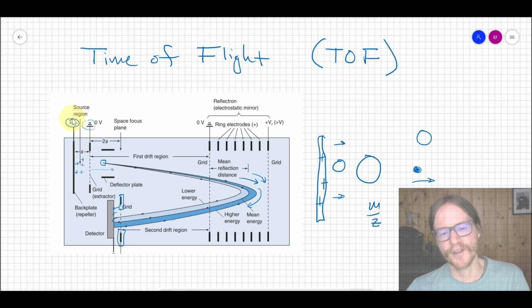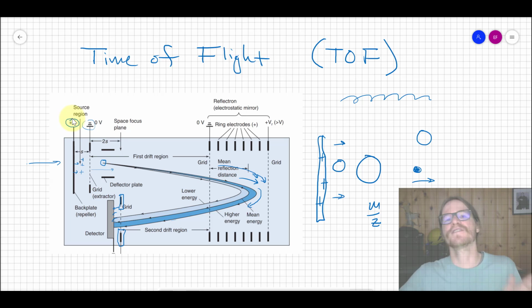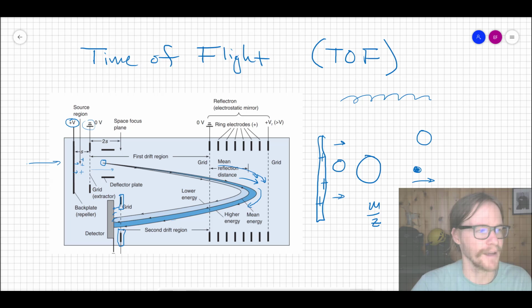And so the principle is very different. Instead of using a radio frequency electrostatic potential applied between 4 rods to change the stable trajectory of an ion, here we're really allowing everything to go through, but they're going through at different rates based on that original push that they get from the repeller electrode. They penetrate further into the set of ring electrodes or less far depending on their mass to charge, and they disperse into a staggered series of ions that strike the detector, and that's the basis of how this type of time-of-flight mass analyzer works.